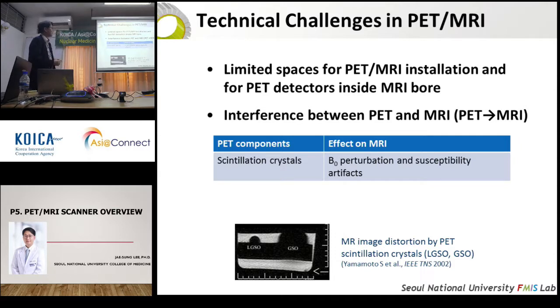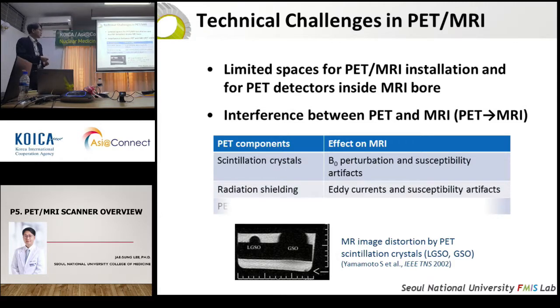Actually, there is also interference in the reverse direction. Some of the scintillation crystals, mostly those with a gadolinium component, like LGSO and GSO, can perturb the MRI field and can also cause some susceptibility artifacts. Some radiation shielding materials used in PET also cause eddy currents and susceptibility artifacts as well. The electric signals from the PET electronics and cables also interfere with the RF detection. So there are many challenges and many interferences that we should avoid in the integration of PET and MRI.